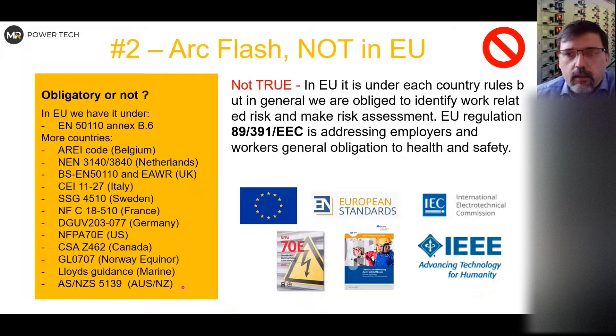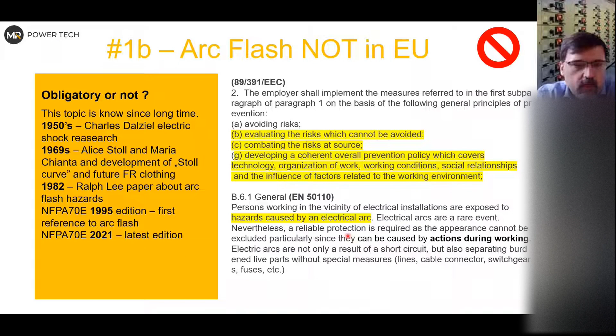So it's not risk specific, the regulation from the European Union, EEC. We have to combat the source, we have to make the policy and so on. But EN 50110 is much more specific. It generally says, if we work in or visit an electric station, we are exposed to a hazard caused by an electric arc. And more, you can read it, everything, but it is written there. It is referring to NFPA 70E, even IEEE 1584, as a good source of information. So it is not true, as we have it in Europe.